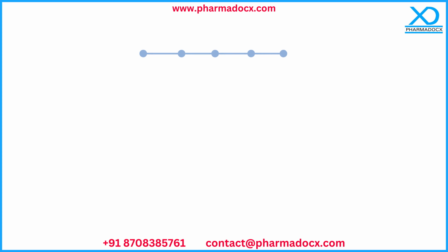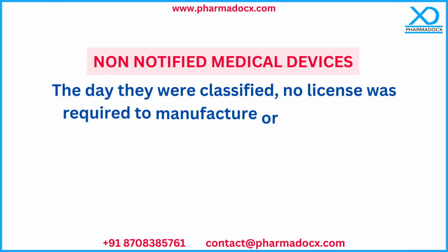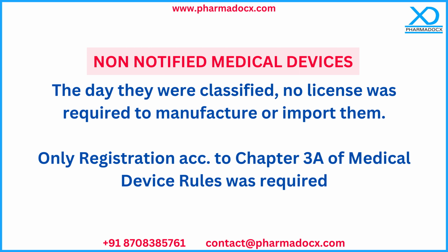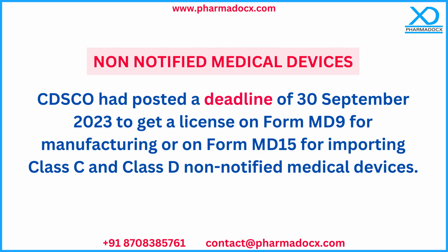In the period of 6 years from 2017 to 2023, certain medical devices were classified as Class C and Class D medical devices. These devices were also called non-notified medical devices, meaning the day they were classified, no license was required to import or manufacture these devices, only a registration as per Chapter 3A of the medical device rules was required. For these non-notified medical devices, the CDSCO had posted a deadline of 30th September 2023 for obtaining the license to manufacture Class C and Class D non-notified medical devices on Form MD9 or an import license of Class C and Class D medical devices on MD15.